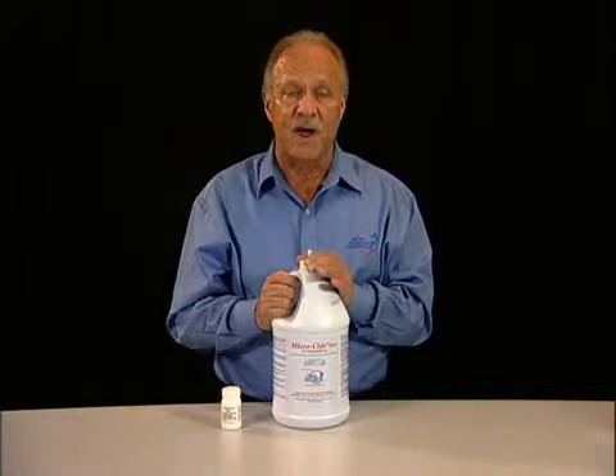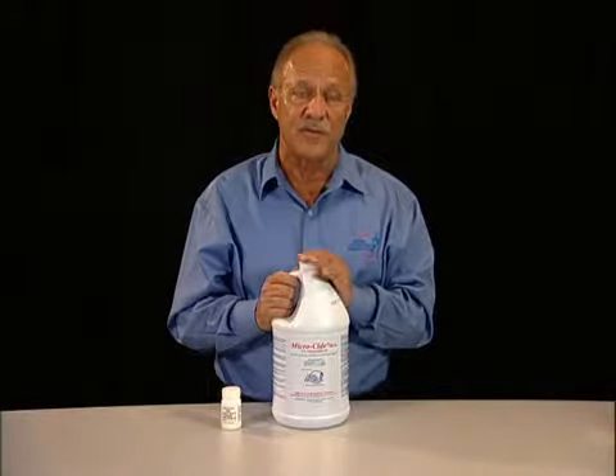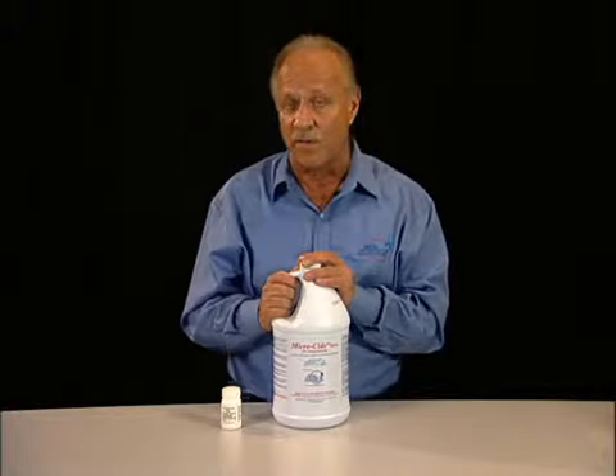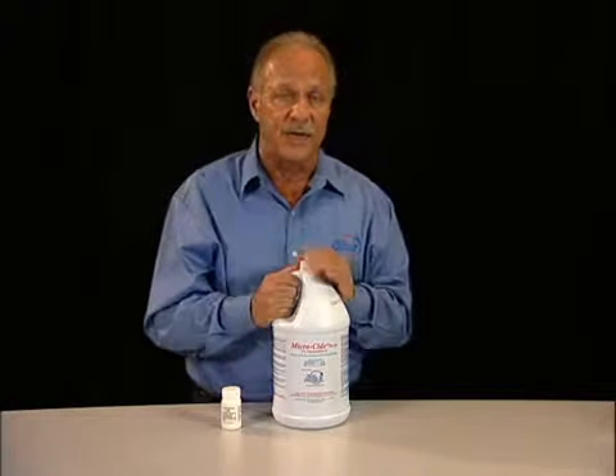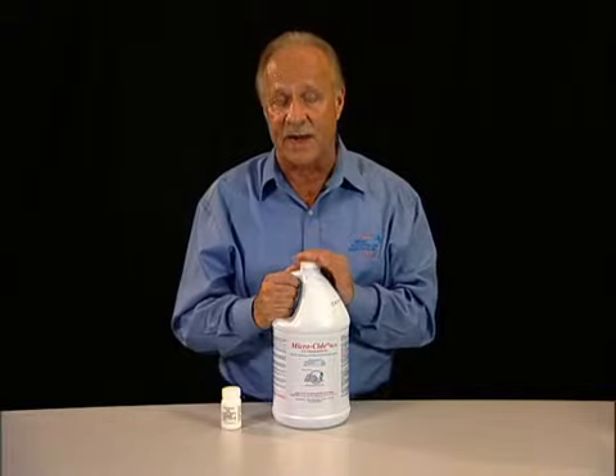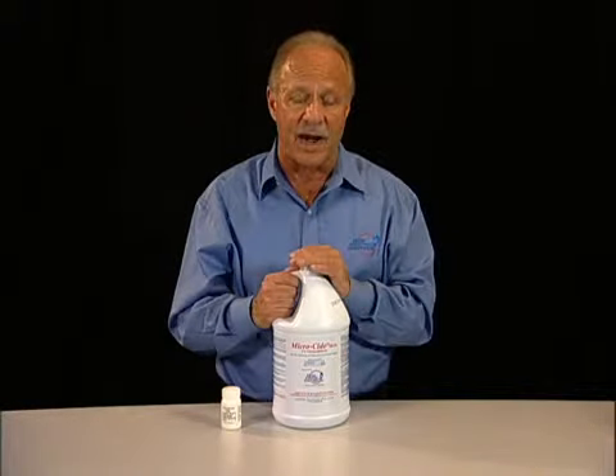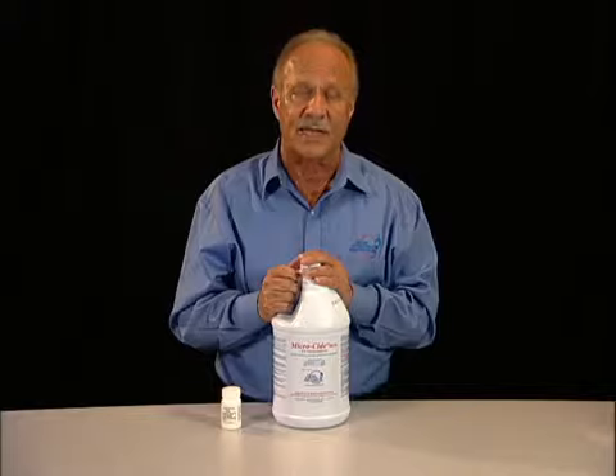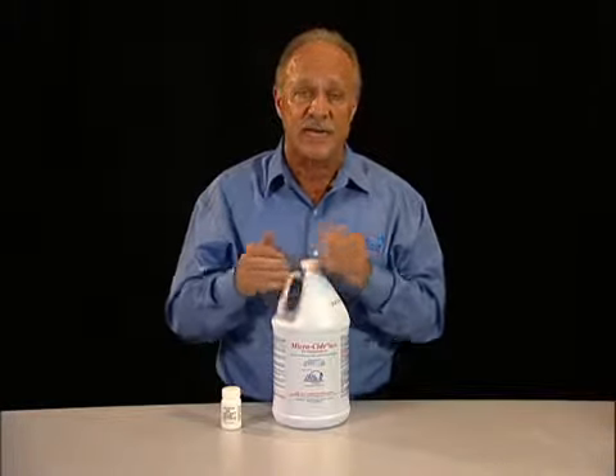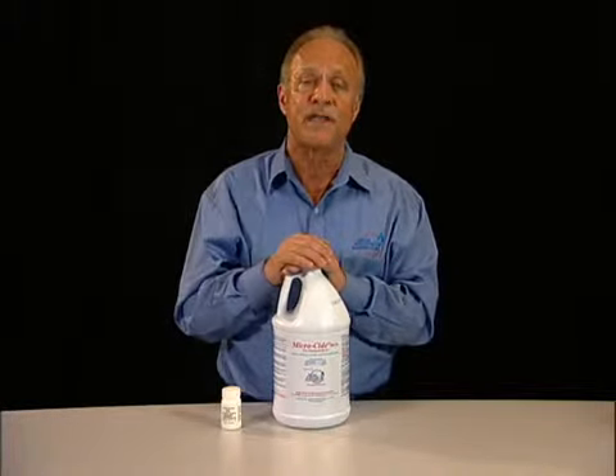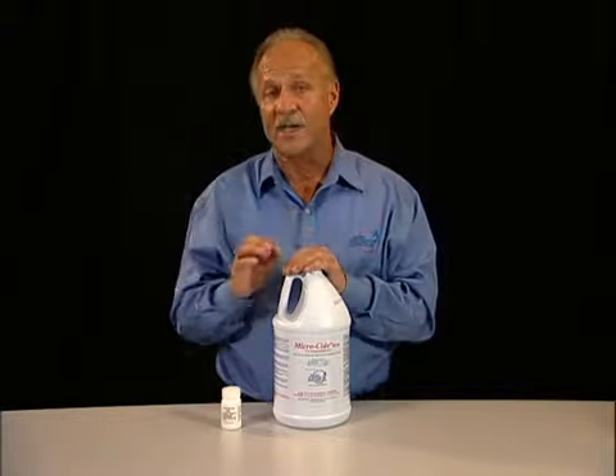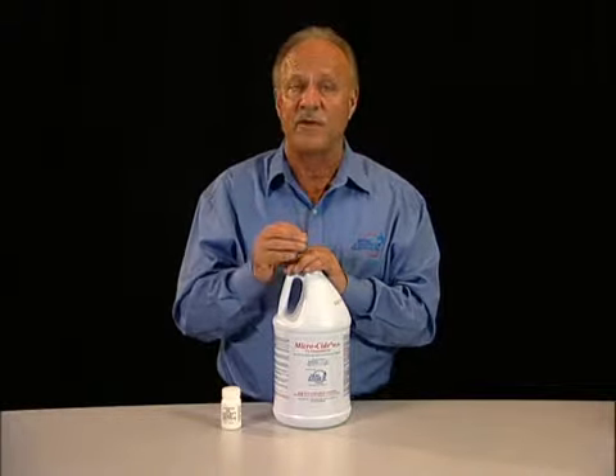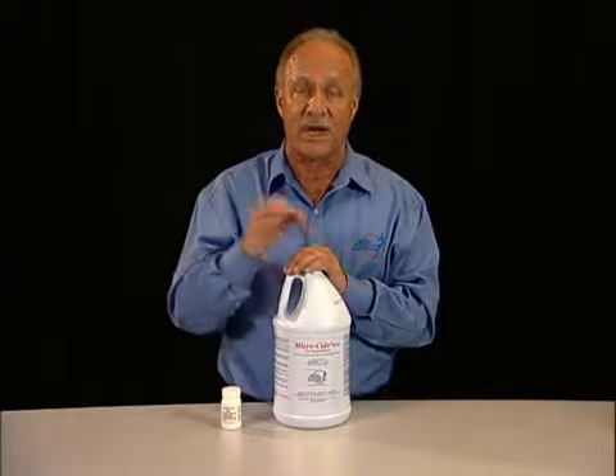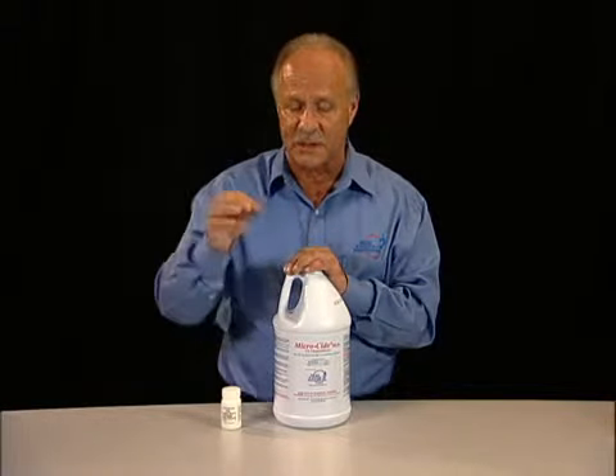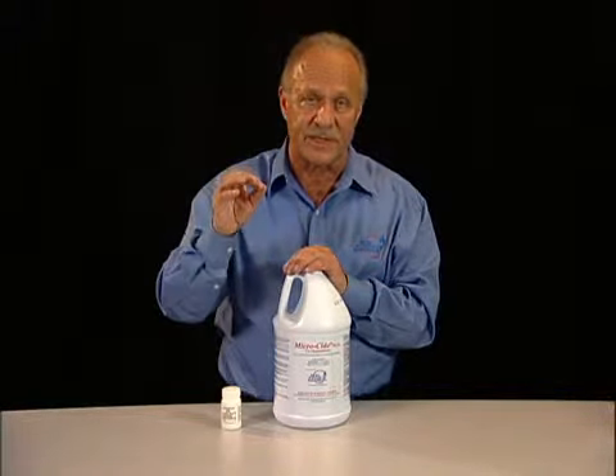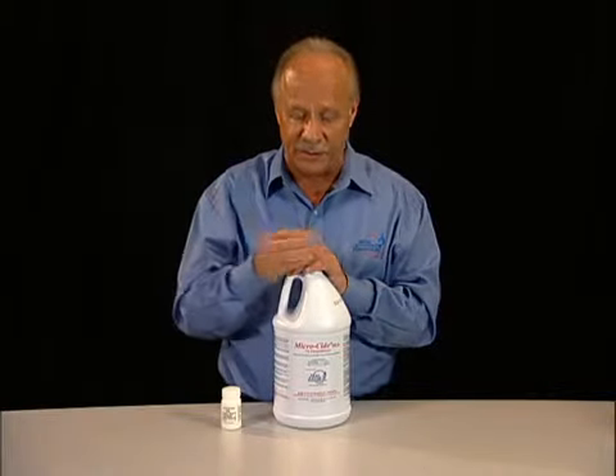The Cidex product consists of 2 particular formulas. One is what we call a 14-day product, and the other one is what we call a 28 or a 30-day product. A 14-day product means that once you've activated the product and prepared the solution for use and begin to use it, you can use the product up to 14 days on the condition that each day you monitor the product using a strip to make certain that the product is still working. This is sort of like a litmus test where you simply dip a piece of paper into the solution and look for a color change.